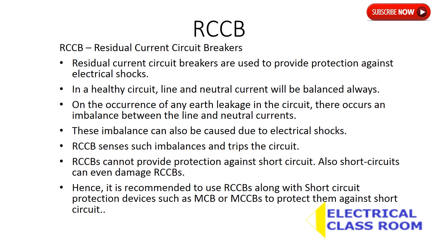Residual current circuit breakers cannot provide protection against short circuit. Also, short circuits can even damage RCCBs. Hence, it is recommended to use residual current circuit breakers along with short circuit protection devices such as MCBs or MCCBs, to protect them against short circuit.